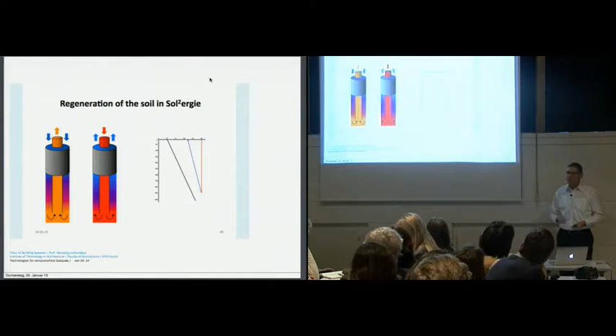But now we developed, because of a mistake, a solution: we use a flexible membrane. We insert a folded flexible membrane into the hole and expand it with water, and this water is used as a circulation system for the whole installation. We have an overpressure of 2.5 bar in every earth probe system, from the expansion tank - every system has an overpressure of 2.5 bar. This pressure presses the membrane against the wall, protecting the wall from damage and protecting the circulation from water at the lower stages and so on.